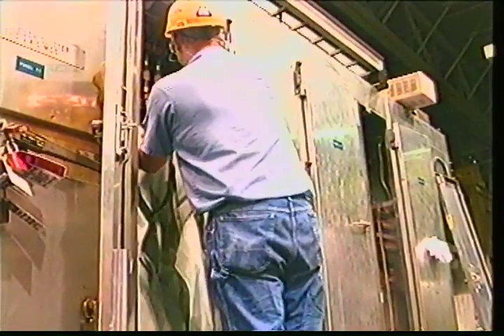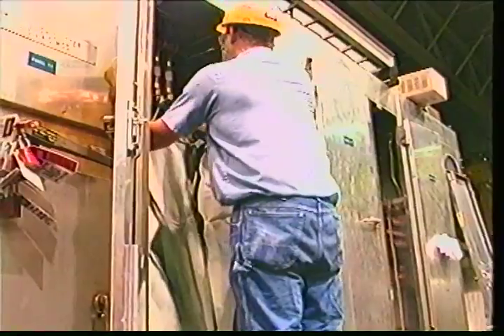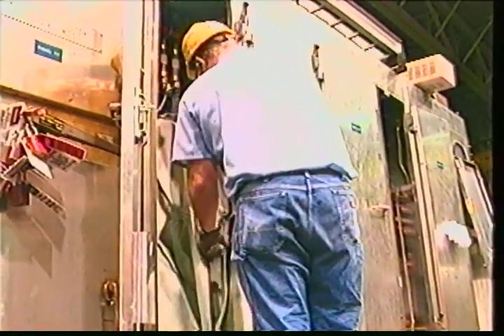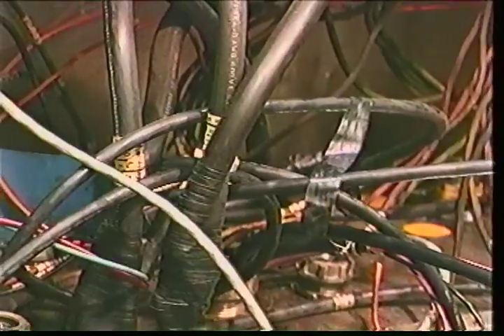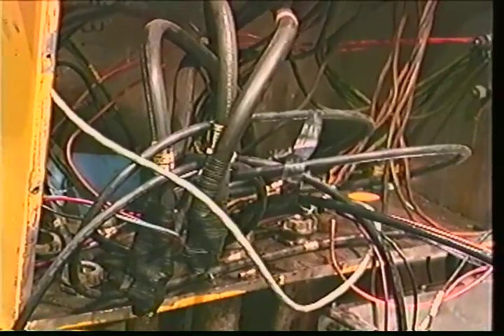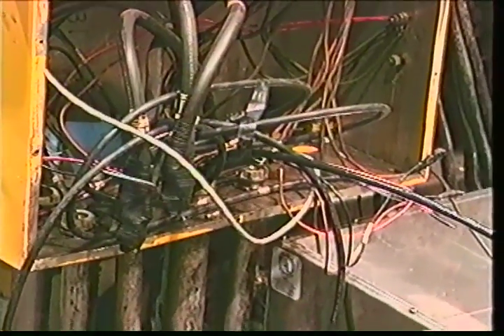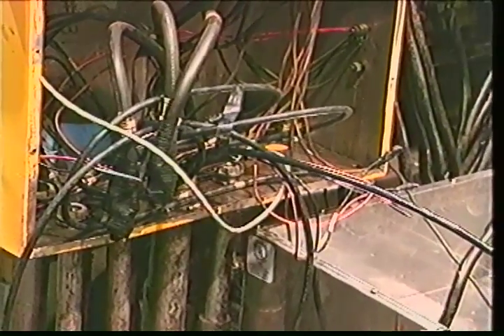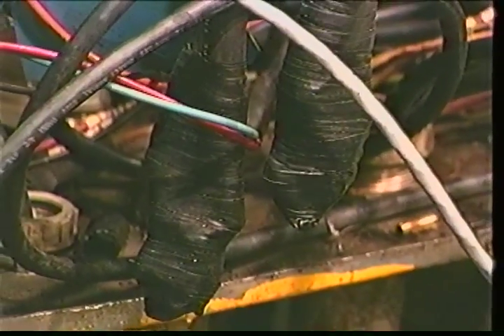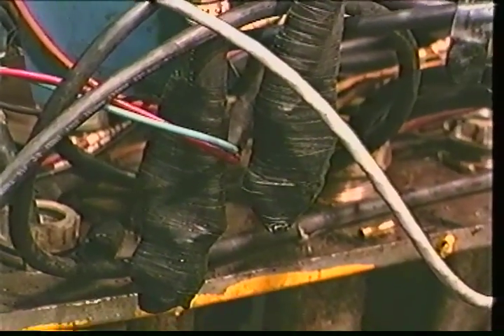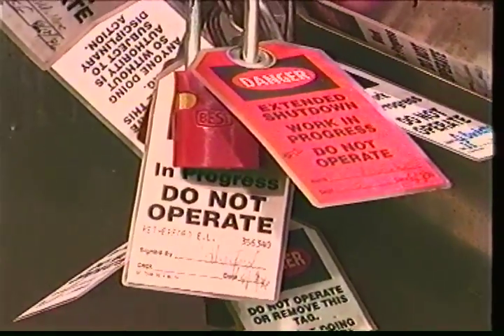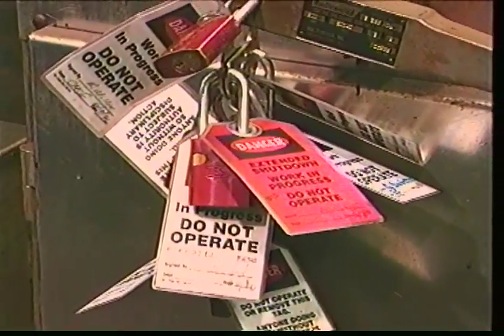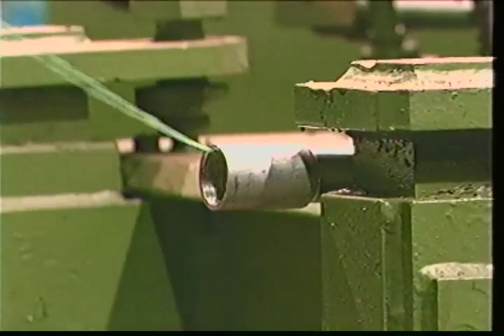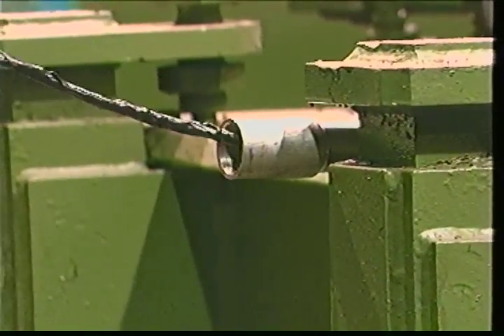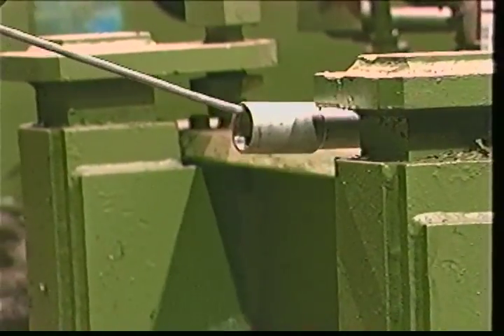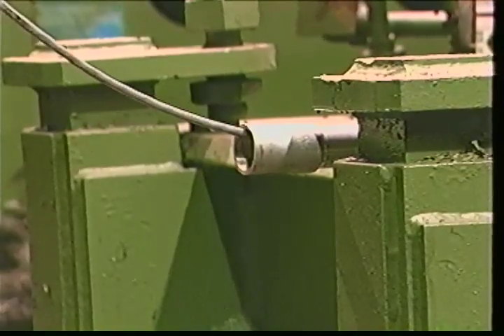When performing demolition, removal, replacement, or new installation type work where exposed electrical wiring could pose a hazard, follow the safety rules for electrical wire isolation. This requires the proper isolation of exposed electrical wires that have a potential to be energized. The exposed wiring is required to either be removed if not needed, or protected, taped, insulated if the wiring is to be reused. Power sources are to be disconnected, locked out, tagged out, and any exposed wiring properly secured. If the system is to be energized with the unused wiring in place, the wiring must be properly insulated and concealed in conduit, junction boxes, or otherwise isolated from contact.